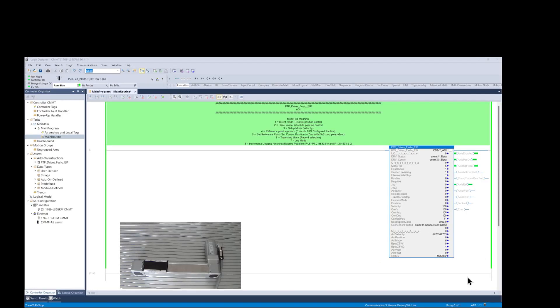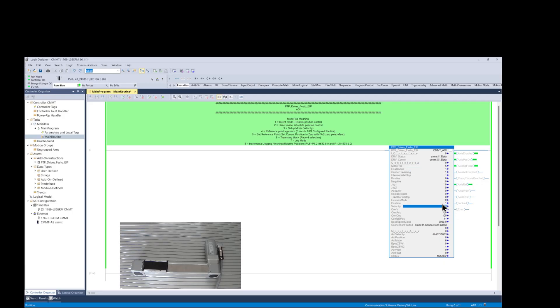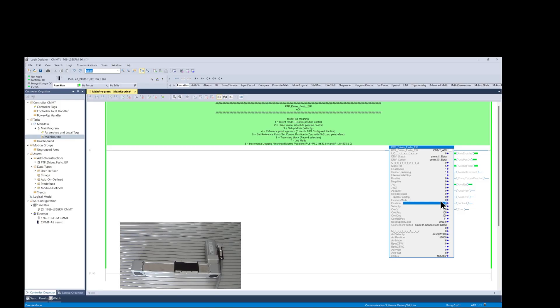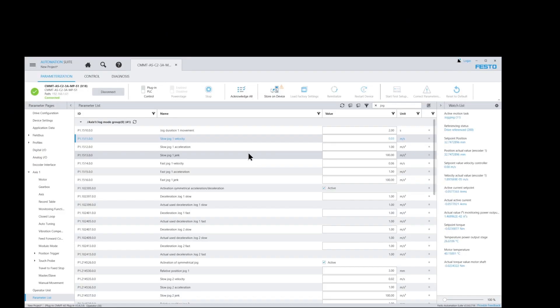Next we begin by changing the ModPause value to 6, then position value to 1, which means that we are executing move 1 of the record table. And then we set the execute mode value to 1 to begin the move. When the move is done, we change the position value to 2, which means that the second move of the record table will be executed. And then we set the execute mode value to 1 to begin the move again.